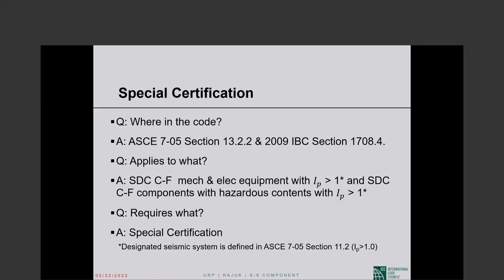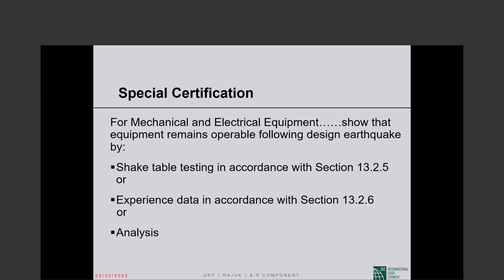So what is required for special certification? For mechanical and electrical equipment, you must show that the equipment remains operable following the design earthquake, and this showing has to be by shake-table testing in accordance with such and such, experience data in accordance with 13.2.6, or analysis. The basis can be shake-table testing, experience data acceptable to the building official, or analysis—though the analysis choice is kind of restricted and cannot always be used. The purpose of the shake-table testing and so forth is to show that the equipment remains operable following the design earthquake, and the special certificate will state exactly that.